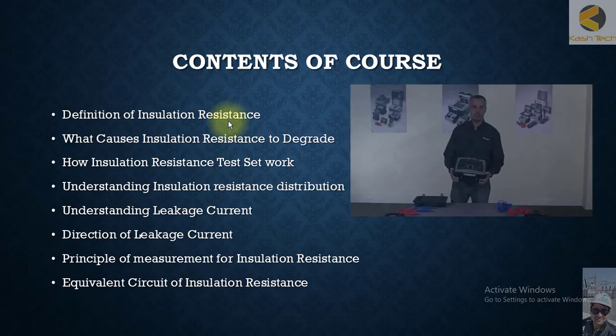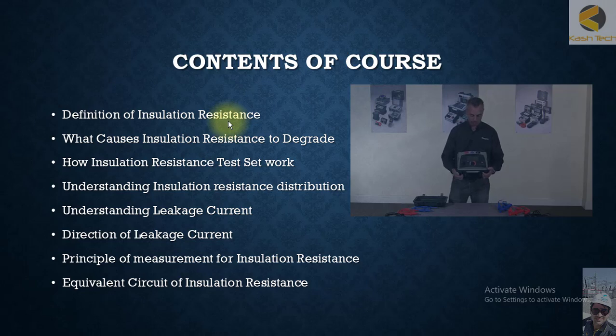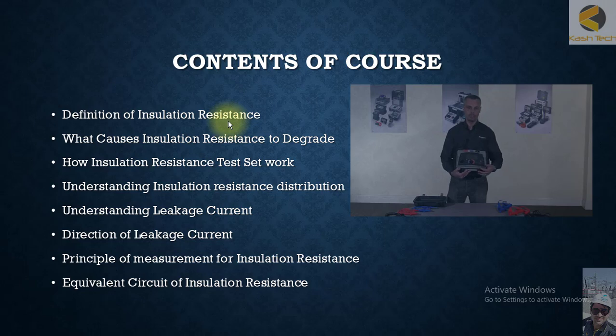This is also the most important test for testing insulations. The most commonly known method is spot testing, in which you select the voltage, inject the voltage, and check the reading. However, this is not the right method in all conditions and cases. Today we will see how many types of Megger testing or insulation tests we can do.